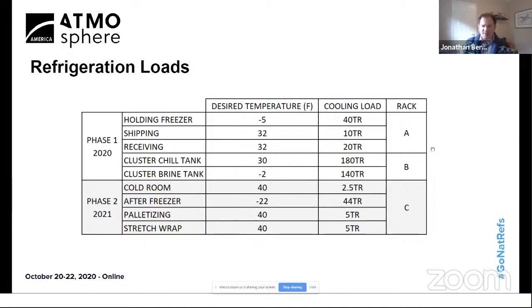The approach taken here was to supply two CO2 transcritical racks. The first, rack A, primarily served the holding, shipping, and receiving areas and their evaporators. The second, rack B, served the brine chilling loads. Our design had to allow for phase two in the near future.